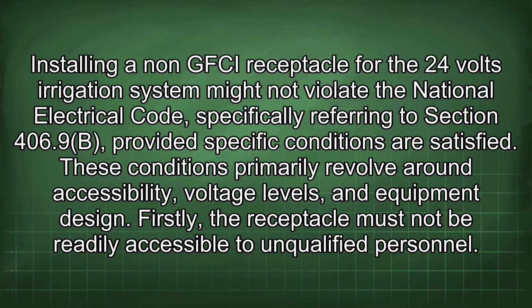Installing a non-GFCI receptacle for the 24 volts irrigation system might not violate the National Electrical Code, specifically referring to Section 406.9b, provided specific conditions are satisfied. These conditions primarily revolve around accessibility, voltage levels, and equipment design.